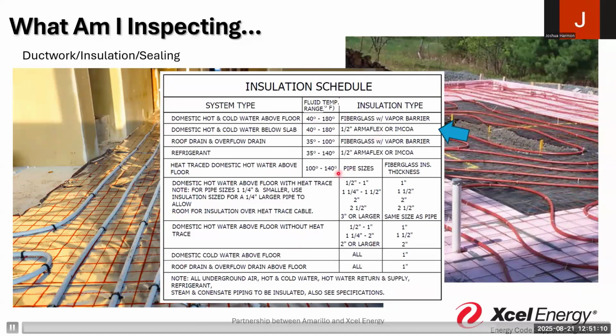A lot of times we see a depth identified, a thickness calculation - we see here this is a half-inch Armaflex, or just the phrase fiberglass, half inch, one inch, all this. What we need to do is more than just provide that size, but also provide the thermal resistance value. As an inspector, I need to know not just that it's a half-inch thick, but that it's providing R3, so that I know it's going to provide the level of condensation control I'm looking for.